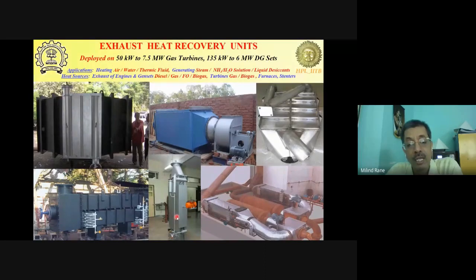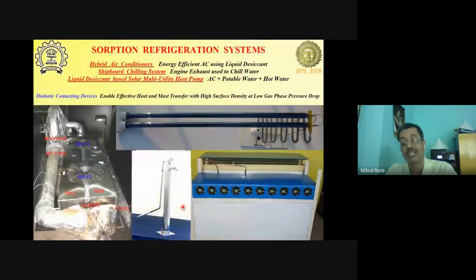which is in Mumbai. And they used to open up their conventional shell and tube heat exchanger every day to clean up the passages. And after we deployed this unit, they were able to generate steam for humidifying the baking tunnel. The chief engineer sent us a note saying that they have not opened the system for more than 3 months. And they wanted one more unit, so we built another unit with all the learnings from the first deployment, and then licensed the technology for them to multiply them in their other 16 facilities. So this was about heat recovery.